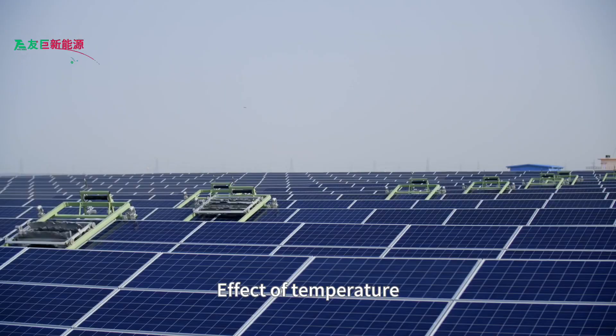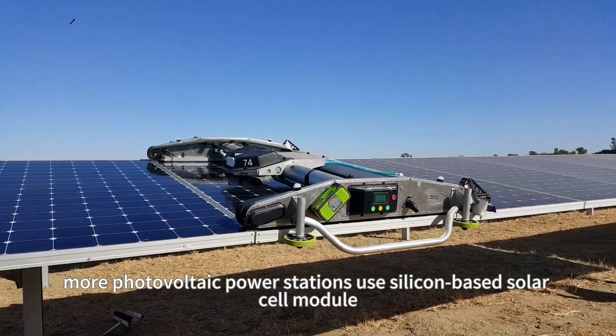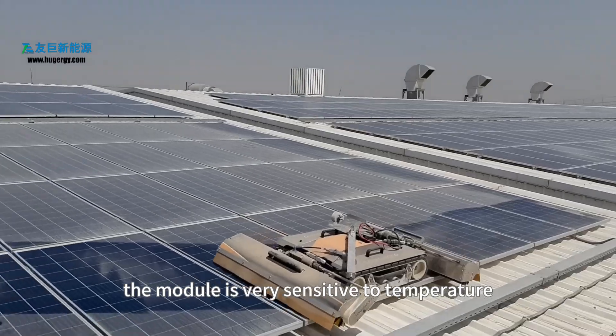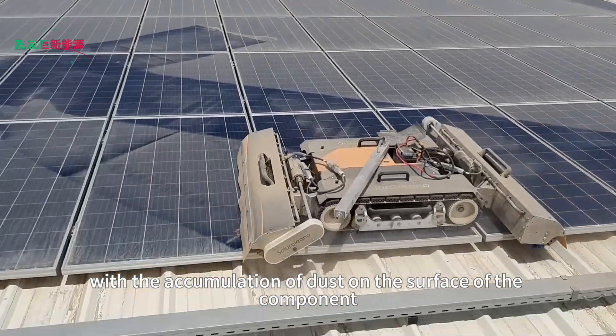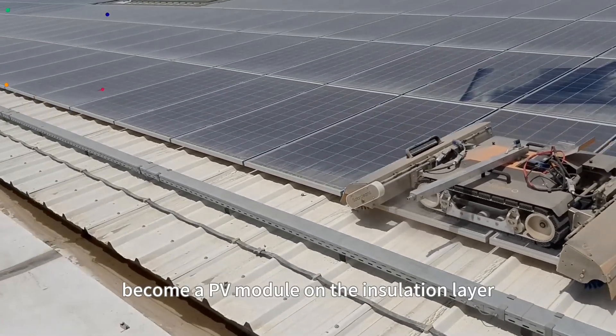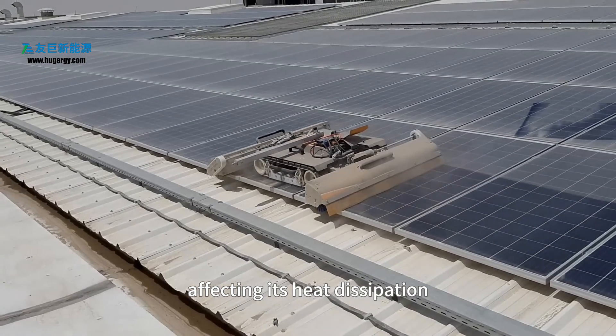First, effect of temperature. At present, more photovoltaic power stations use silicon-based solar cell modules, and the module is very sensitive to temperature. With the accumulation of dust on the surface of the component, it increases the heat transfer thermal resistance of the PV module, becoming an insulation layer on the PV module and affecting its heat dissipation.